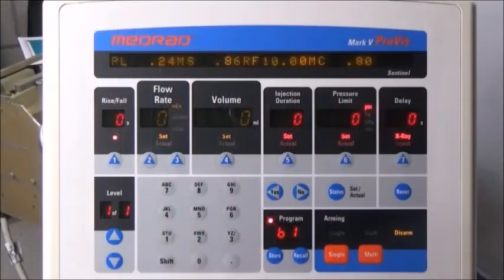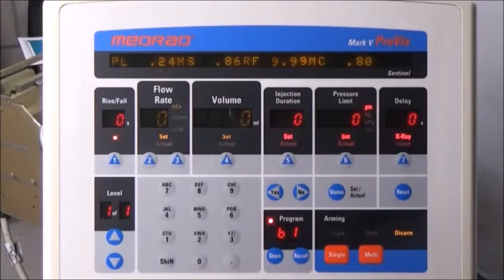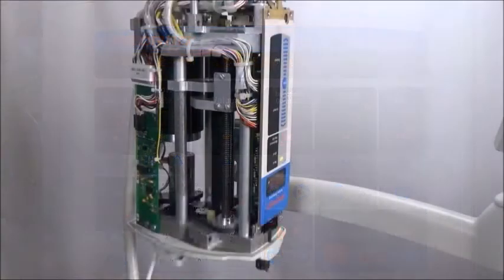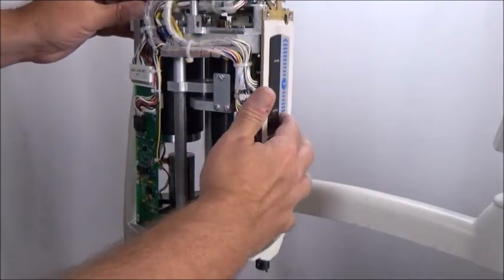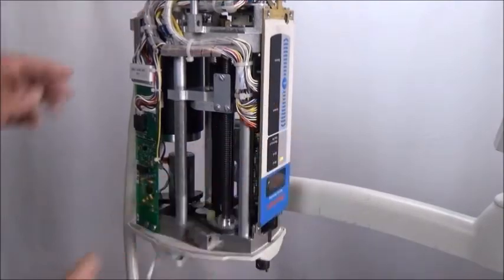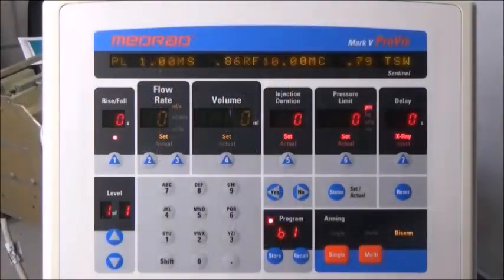Now we can move the MS plate until you get a reading of 0.86 to the right of MS on the display. Now, using the forward button on the injector head, run the plunger plate into the MS plate at full speed, then check the PL voltage on the display. It should be exactly 1.01 volts DC.